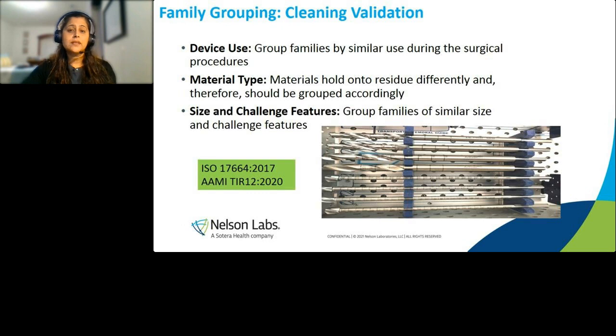Family grouping is another common factor used for cleaning validations, where if you have a whole area of instruments like that, these are drill bits that look exactly the same, but the ends are different, the lumen sizes are different. We would choose just a few from the family and say that if you can clean that, then you can clean the rest of the devices. Of course, you have to choose what is more challenging to clean, where you're looking for the smallest lumen size. You're looking at the end bits to see what will retain the soil the most.